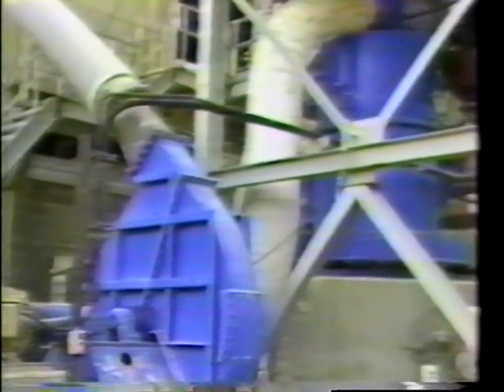This is a sample of the product coming to the burner from the pulverizer. The fineness here is 88 percent minus 325 mesh. Once the material is fine enough, it travels out the classifier at the top, across through this 18-inch diameter pipe, and travels into the exhaustor.